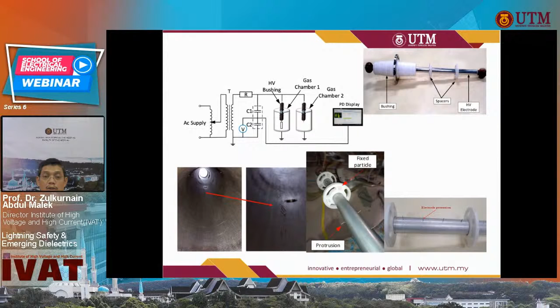And we can introduce a protrusion here, maybe a copper needle at the electrode, as well as floating particles in the chamber itself. And then when we energize the chamber, it will create discharges. So we do two chambers, and then we confirm the byproduct is present not only in one, but also in the other chamber. And as you can see here, we can also use some kind of intelligence to help us identify, based on the gas parts per million content, what the defect inside the chamber is.